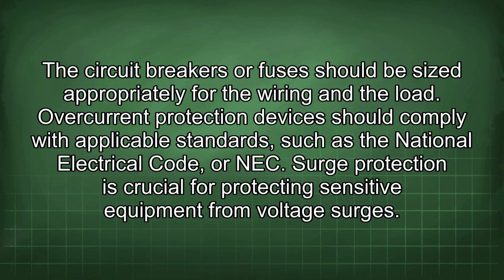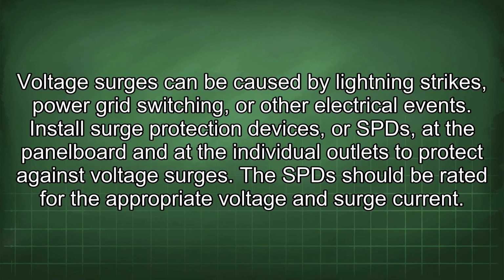Surge protection is crucial for protecting sensitive equipment from voltage surges. Voltage surges can be caused by lightning strikes, power grid switching, or other electrical events. Install surge protection devices, or SPDs, at the panel board and at the individual outlets to protect against voltage surges. The SPD should be rated for the appropriate voltage and surge current.